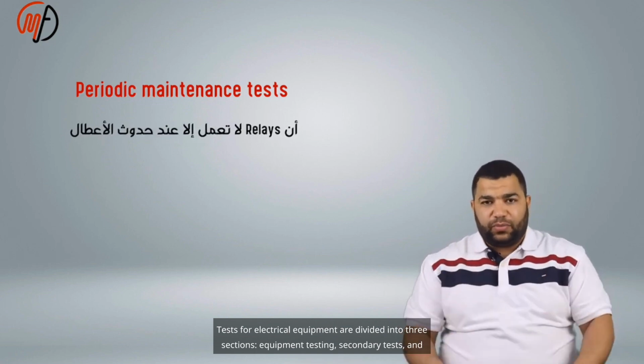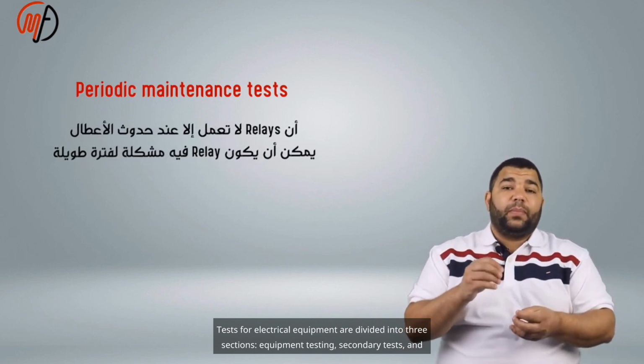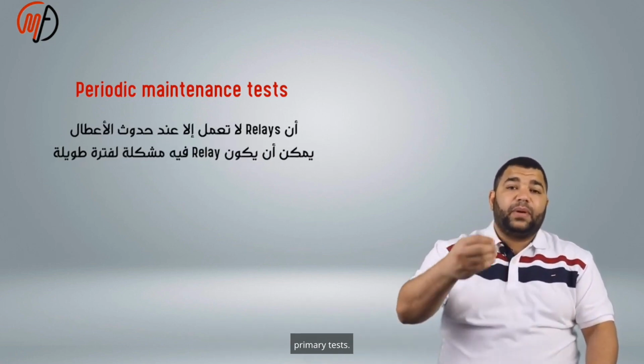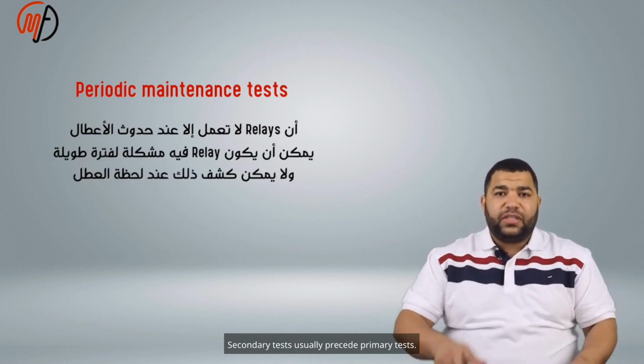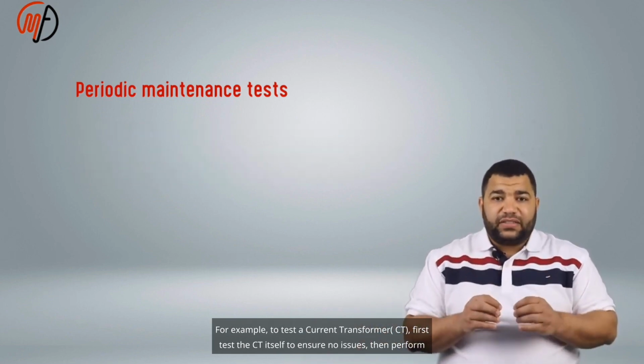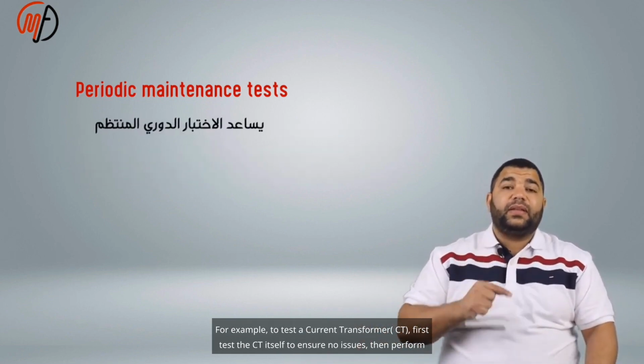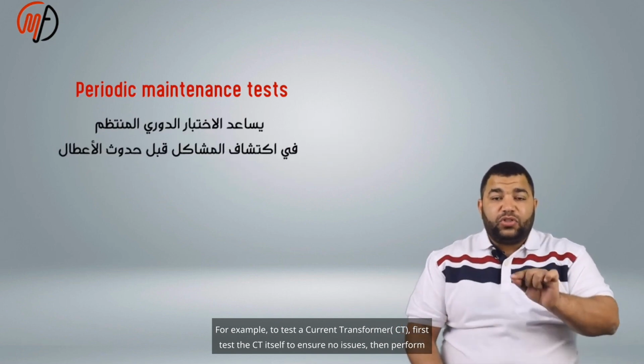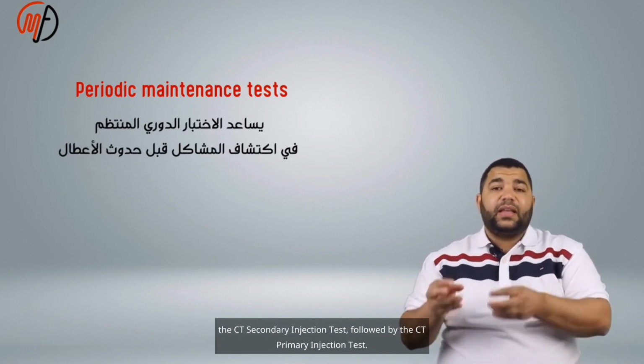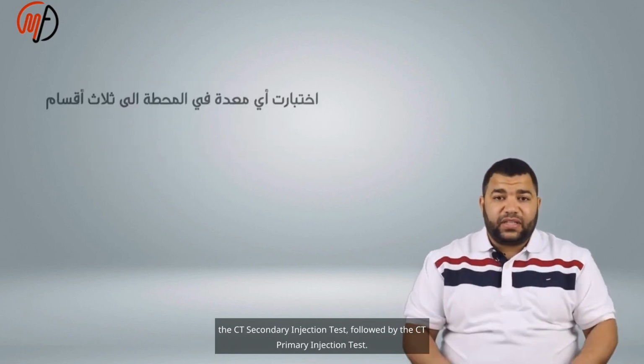Tests for electrical equipment are divided into 3 sections: equipment testing, secondary tests, and primary tests. Secondary tests usually precede primary tests. For example, to test the current transformer, CT, first test the CT itself to ensure no issues, then perform the CT secondary injection test, followed by the CT primary injection test.